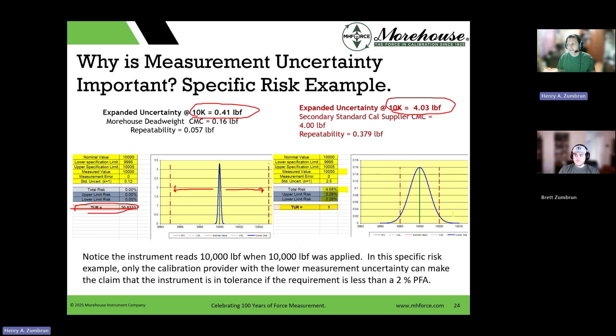But in this situation, there's risk just by doing nothing on this instrument, which had a specification of plus or minus 5 pounds out of 10,000, so 0.05%. In this case, no matter what I do, if my measurement is dead centered over here, I have risk and it's over 2%. In the case to the left, I have forever to still say this is good. In the case to the right, there's a strong chance that I'm going to say something's good when it's actually bad, or bad when it's actually good. If I move the measured value to 10,004, where last time it was 10,000, the story gets a lot different.